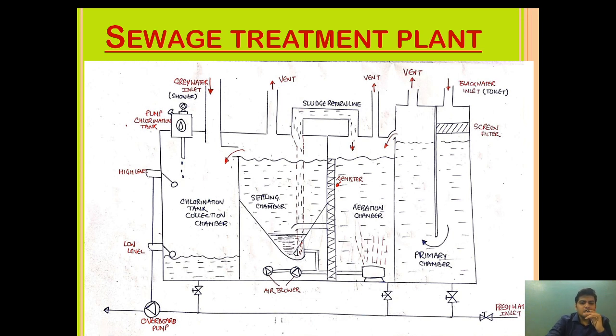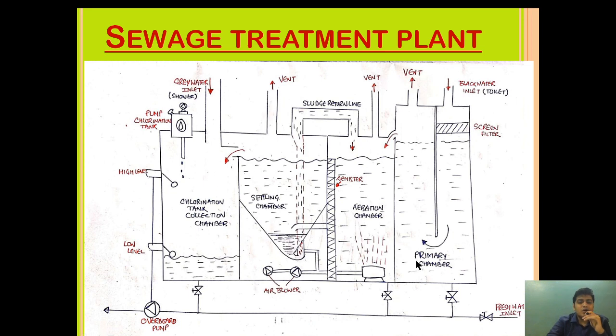Grey water — the water used for bathing — comes directly into the chlorination chamber, not the primary chamber, because this water doesn't contain bacteria and only needs disinfection. Additionally, from time to time the sewage treatment plant must be flushed with fresh water so that any sewage clinging to the surfaces of the plant walls is cleaned off and pumped out by the overboard pump.